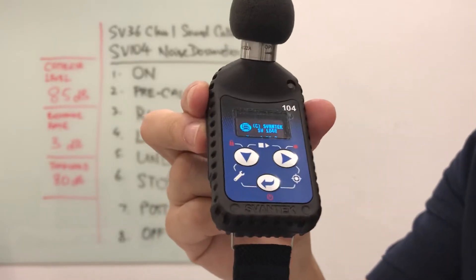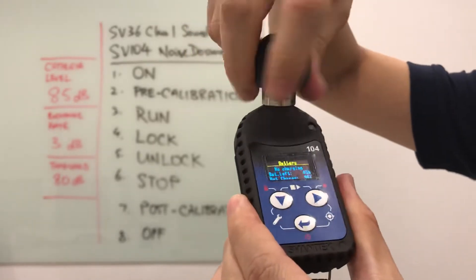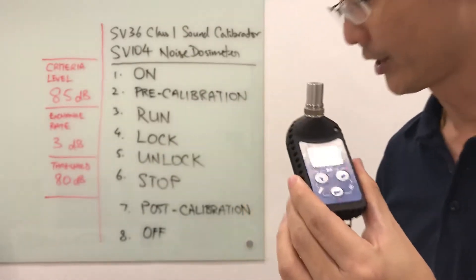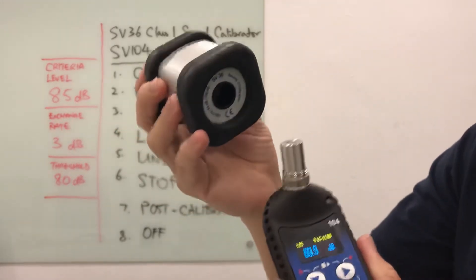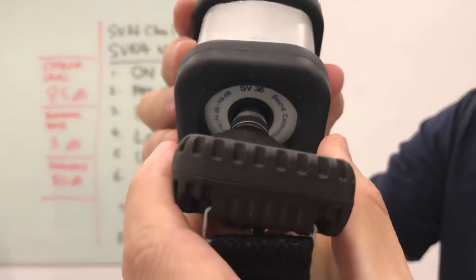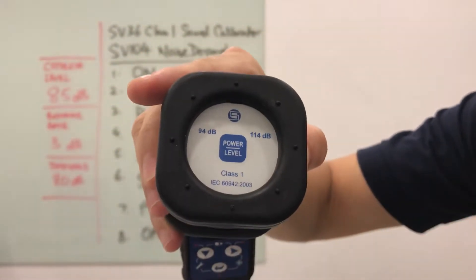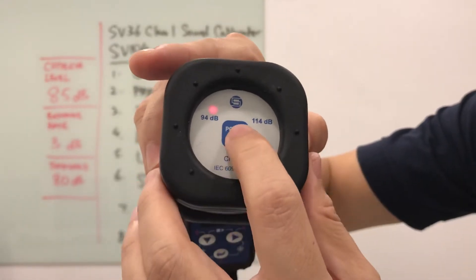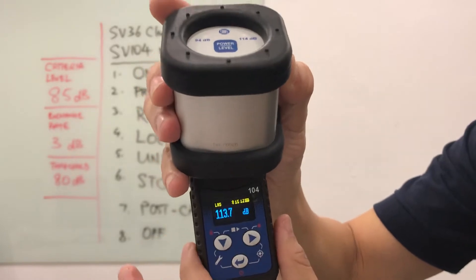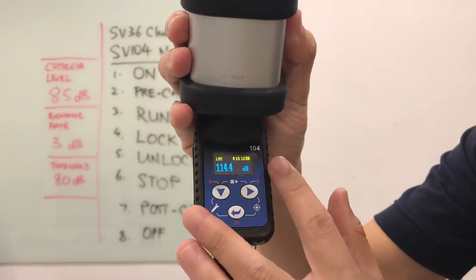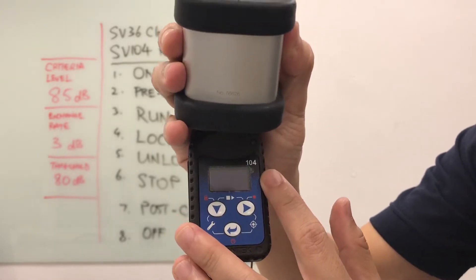Once the device has been turned on, I need to do a pre-calibration. I will unscrew the windscreen and then use a SV36 class 1 sound calibrator and insert it into the mic. The moment I insert it, there is a sensor inside the calibrator that knows I have inserted a sound dosimeter. Because I have set up my noise dosimeter to calibrate at 114 dB, I need to make sure the sound calibrator is set to 114 dB.